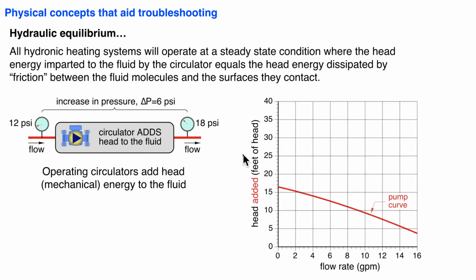And the way we represent the head added by the circulator is with a pump curve. And you can see a typical pump curve where we're plotting flow rate that is passing through the circulator, and we're plotting that against the head energy that's added. And typically the units in head energy in North America, we use feet of head. And just as a side note, where does that come from? It actually comes from foot-pounds of mechanical energy per pound of fluid passing through the circulator. If you take foot-pounds of energy and divide it by per pound, the units of pounds cancel out and we get just a unit of feet.